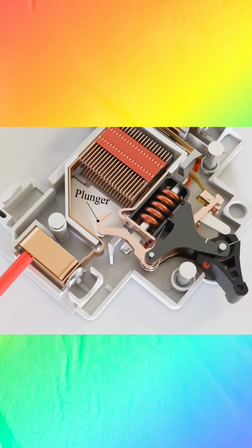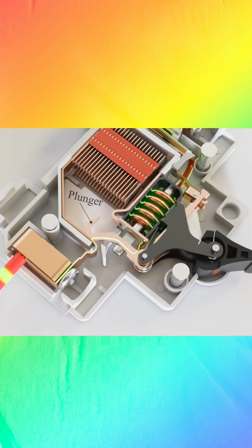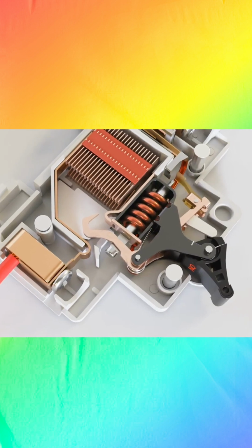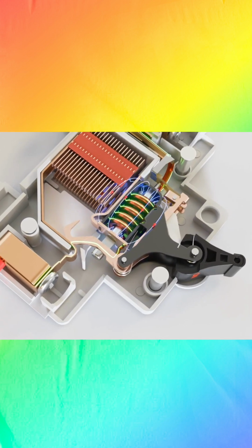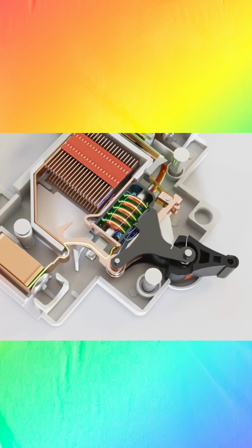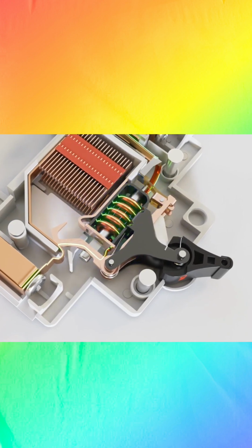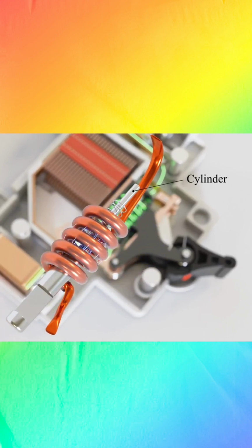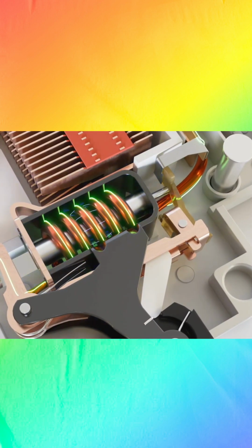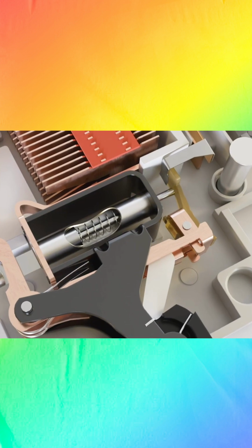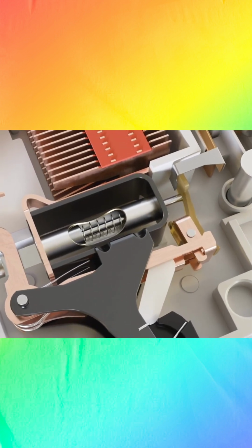A moving part known as a plunger is responsible for making and breaking the connections between the input and output connectors. When current passes through this coil, a magnetic field forms around the coil. As the current passing through the coil is an alternating current, the magnetic field formed is also pulsating in nature. A cylinder made of a ferromagnetic material is placed inside this coil. The magnetic field of the coil exerts a force on the cylinder due to a phenomenon known as electromagnetism. At normal current values, a spring won't allow the cylinder to move because the force developed in the cylinder cannot overcome the spring tension.